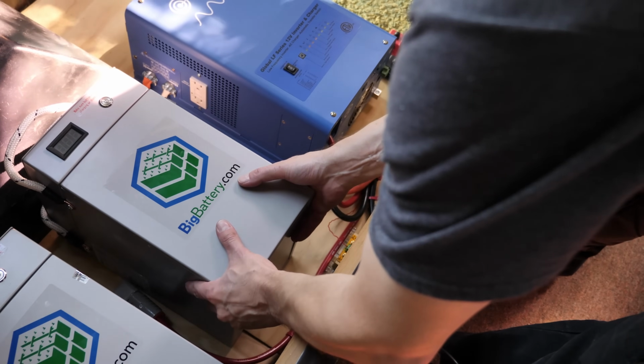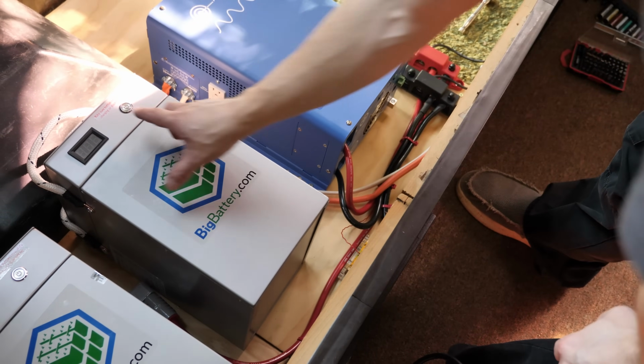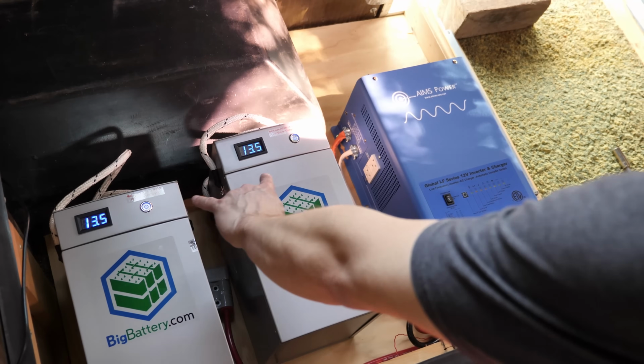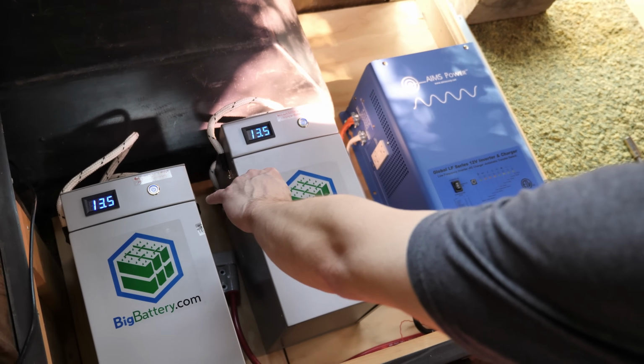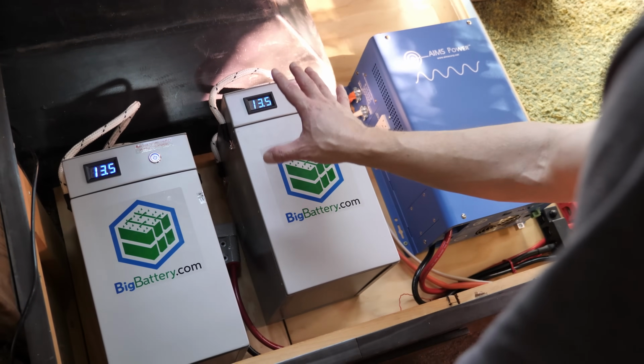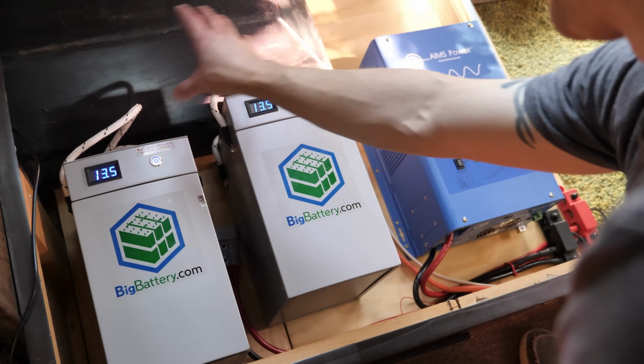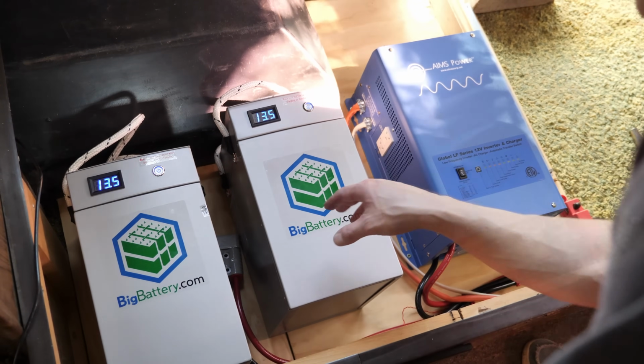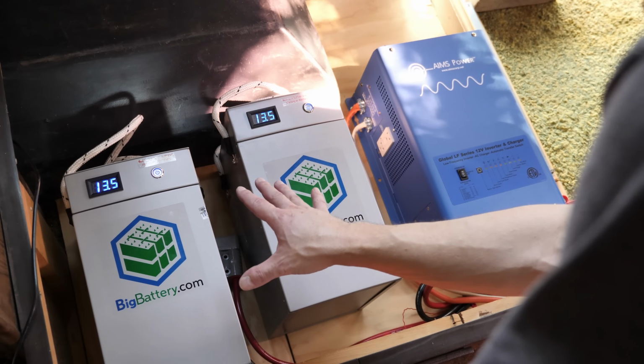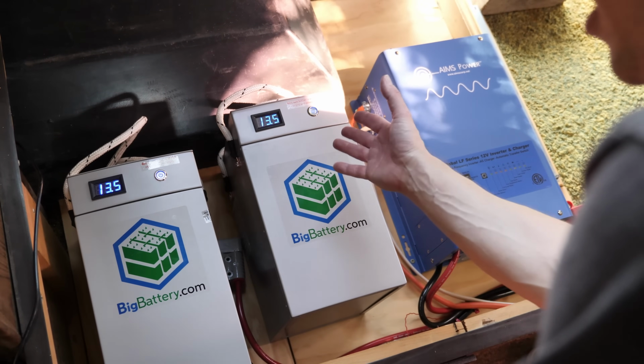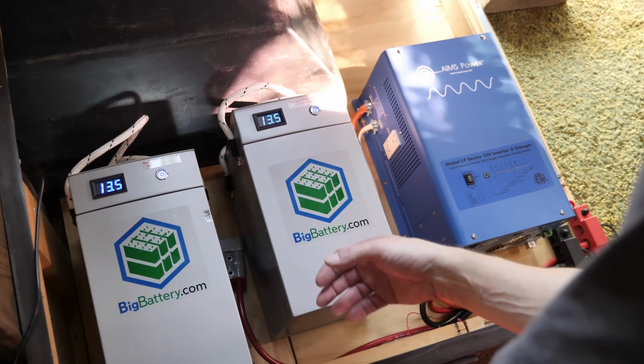Before you connect these 2 batteries in parallel, turn them on real quick and make sure the voltage is closely the same. They can be a little bit off, but the closer the better. Because if one battery's dead and one battery's full, there's going to be a lot of current transfer from one to the other. So if you do find yourself in that situation, go ahead and charge both of them up separately and then parallel them together.